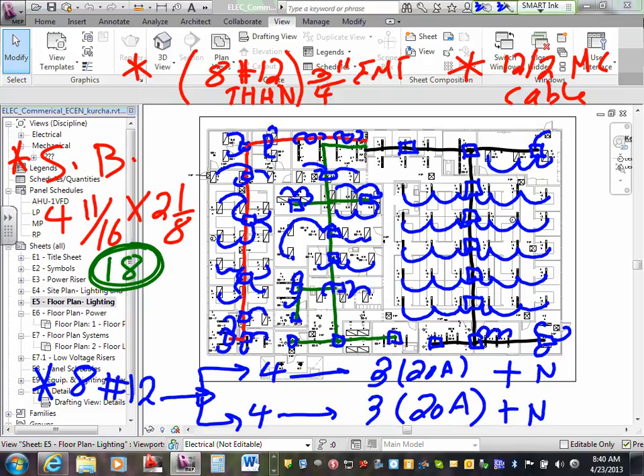Now these type of fixtures, guys, that we used, if you guys remember, these are direct and indirect lights. Direct and indirect lights, they have a stem that comes with them. So for the stem, you have to have some type of tying them together. So you might have to have another tiny little box that comes. So the stem will come into the box, and you go from MC cable from box to box. So you guys need another box above them, because there's direct, indirect light, they're suspended, so you're going to take that stem going all the way.